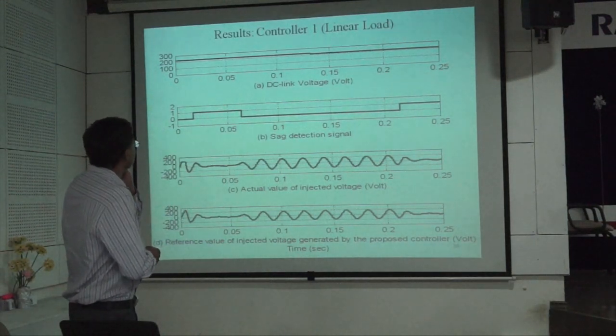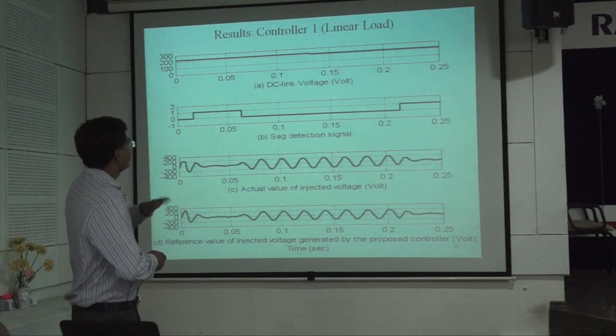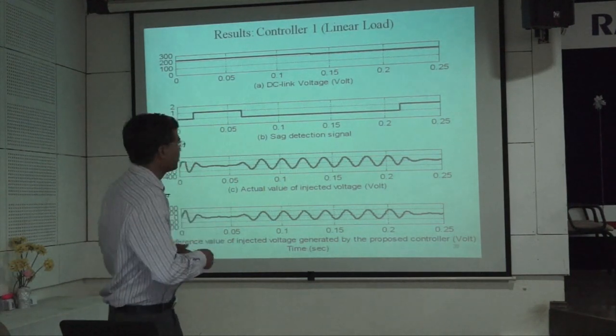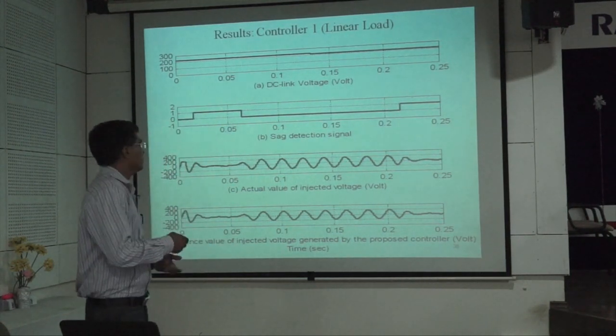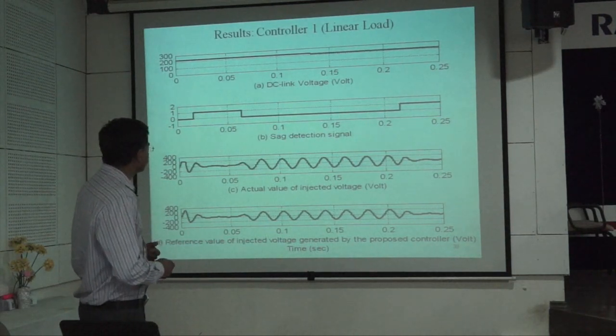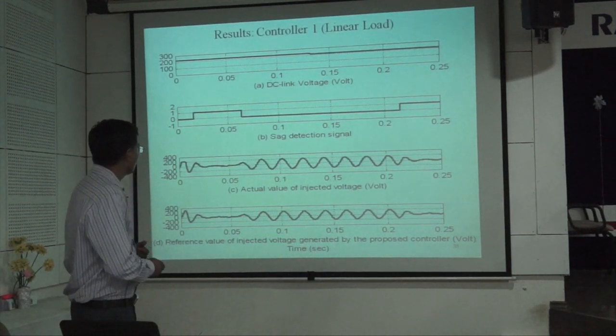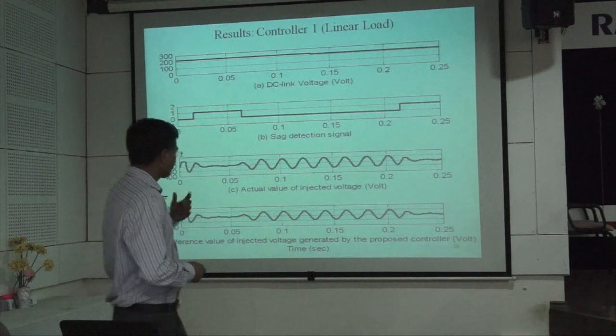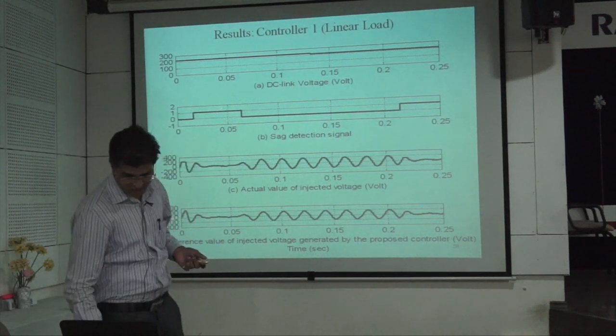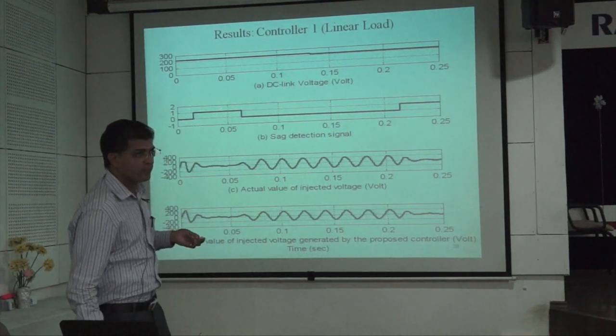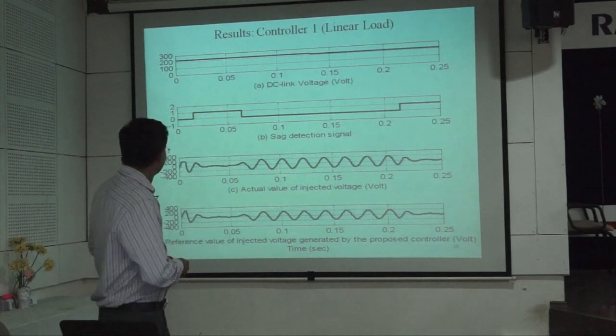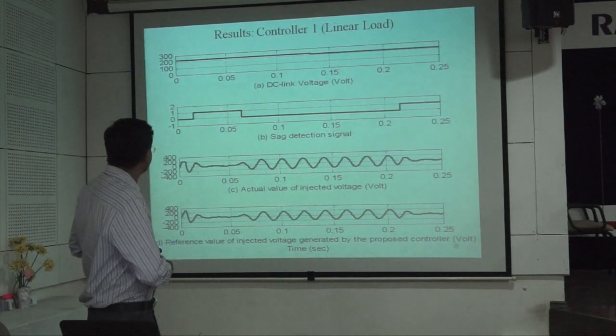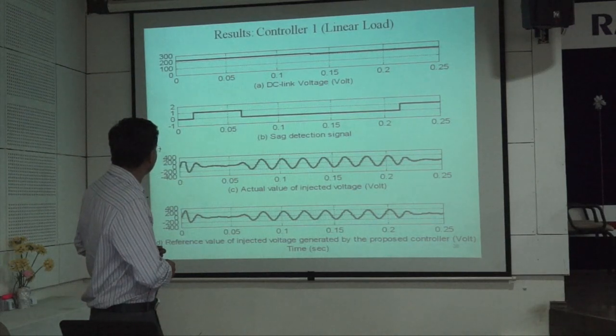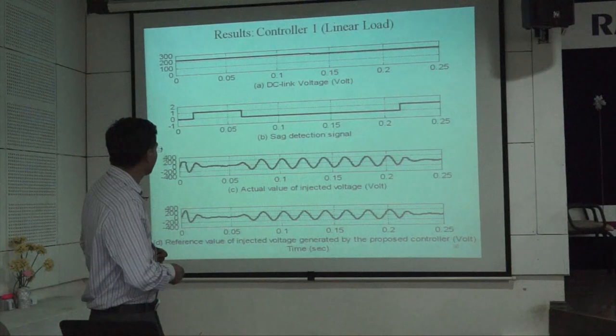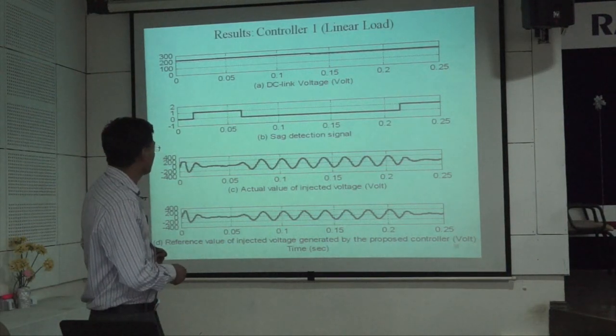The sag compensation is a little bit slower because the controller is a little bit complex. It is based on the feed forward and feedback control system. The actual injected voltage and the reference injected voltage are both nearly the same. So from this analysis, I can comment that the DVR is compensating the voltage. Here the injected voltage is nearly about 200 volt. This is the reference injected voltage, which is also nearly about 200.